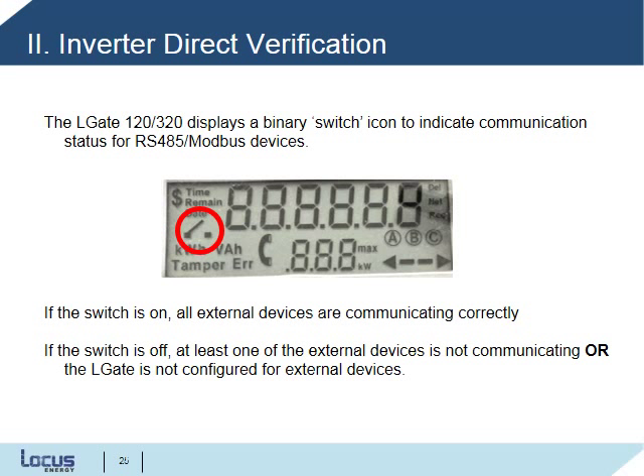If the switch is on, as it's displayed here, all external devices are communicating correctly and are sending data to the LGate. If the switch is off and you don't see it at all, at least one of those external devices is not communicating, or the LGate has not been configured to communicate with external devices.